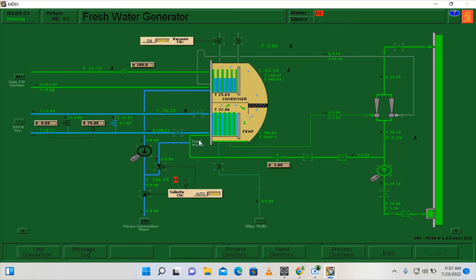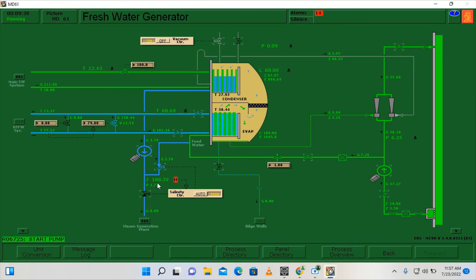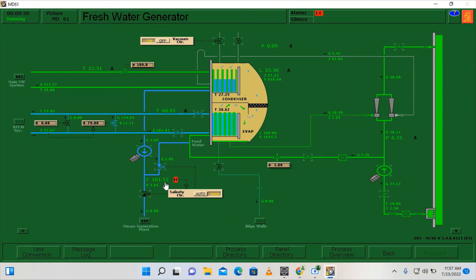Now we are going to switch on the vacuum controller, manually open the solenoid valve for dumping, and turn the distillate pump on. We should observe that the salinity decreases. The alarm set point for salinity is around 15 ppm.